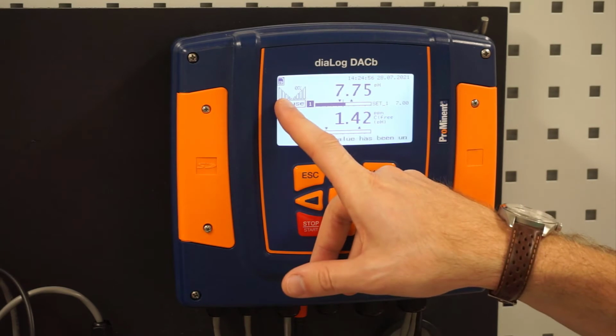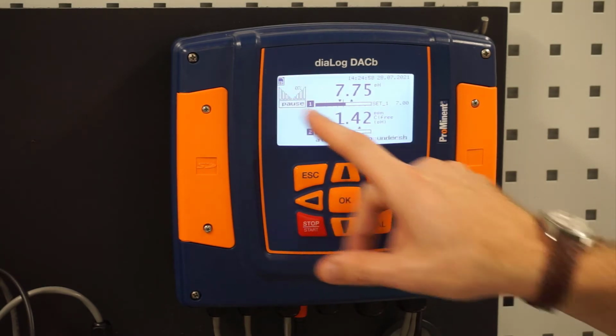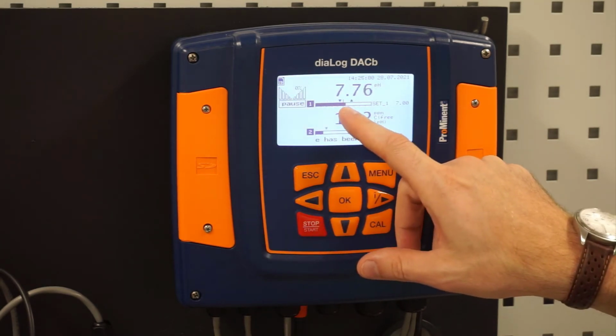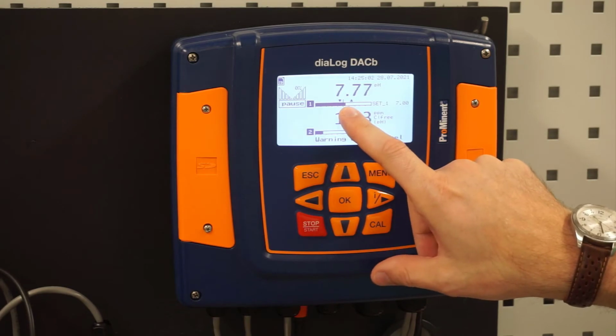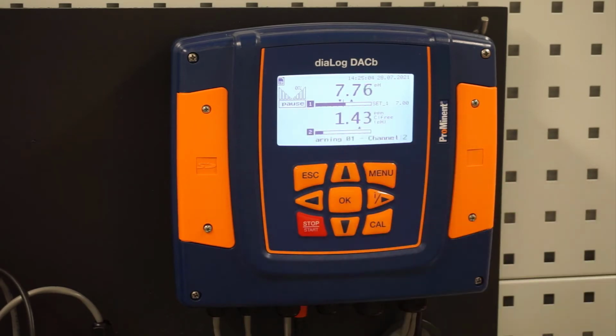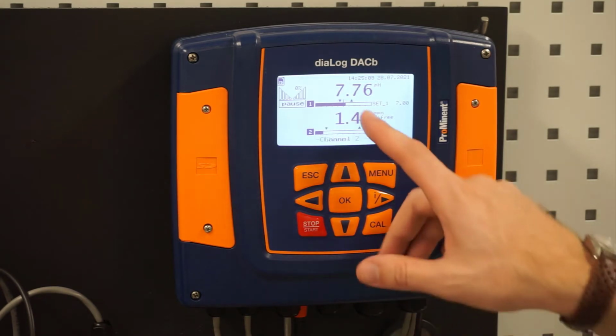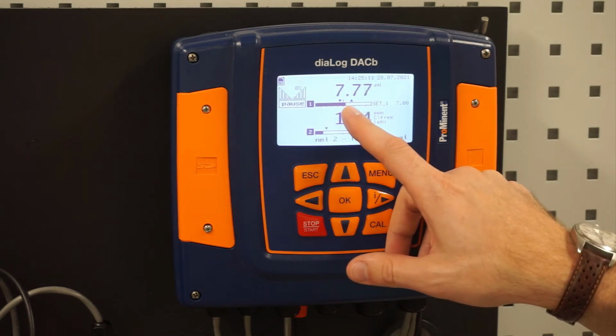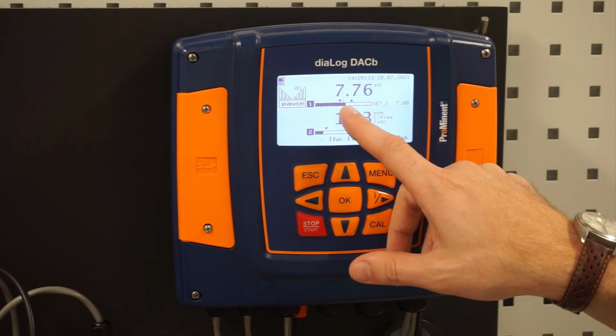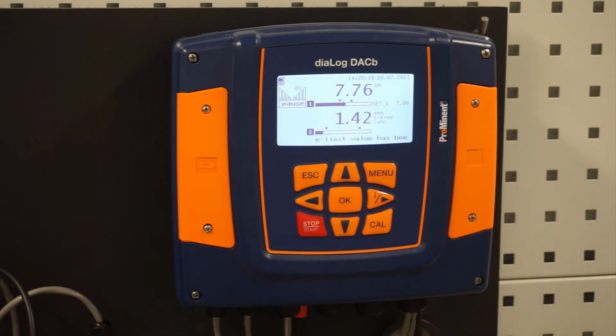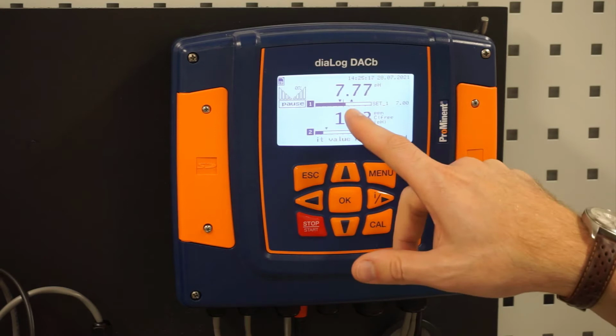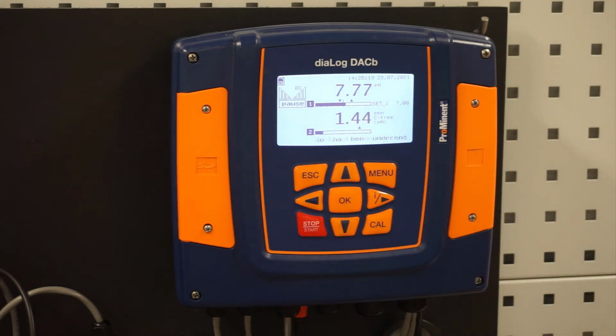Also on here, this would represent us controlling it. So our set point for pH is this up and down line. We are above that, so we're not controlling. We're most likely feeding acid. There's no reason, sorry, we're most likely feeding caustic. There's no reason to feed caustic right now because we're at our set point. If we fed caustic, that would keep raising up the pH value.